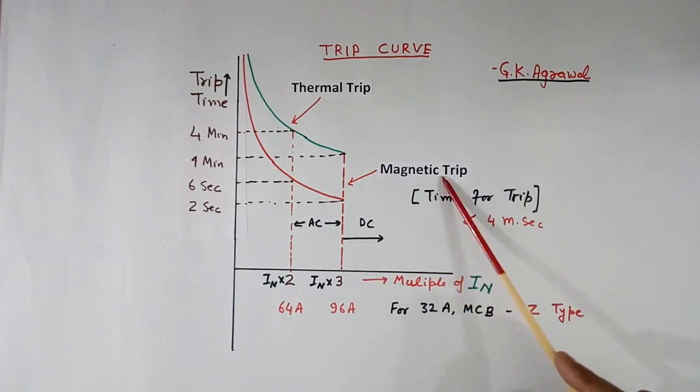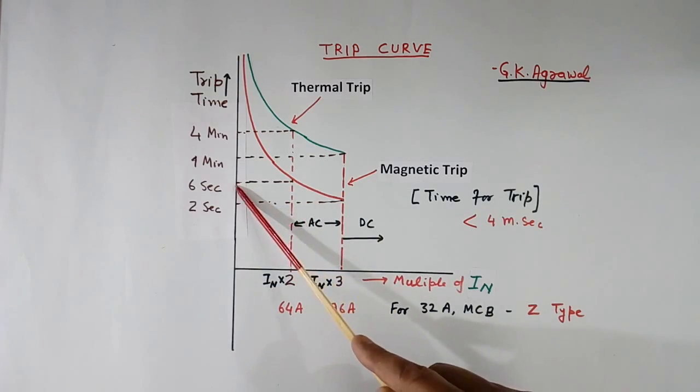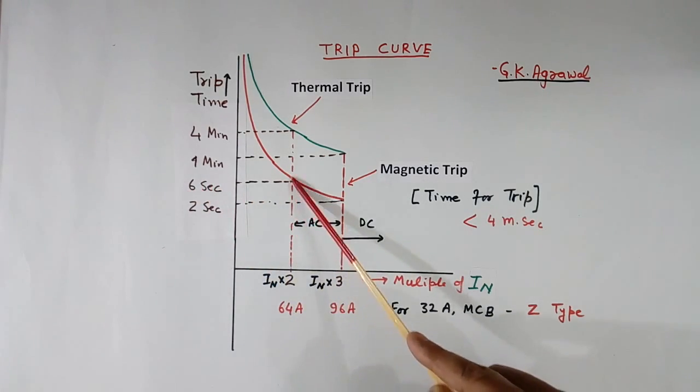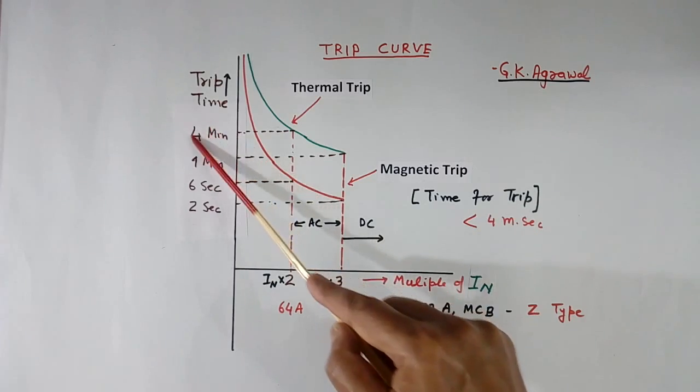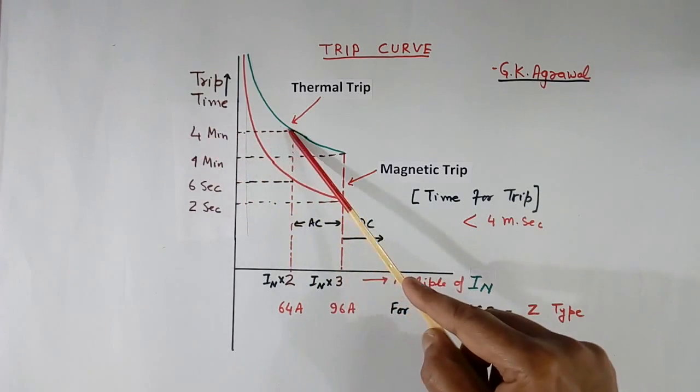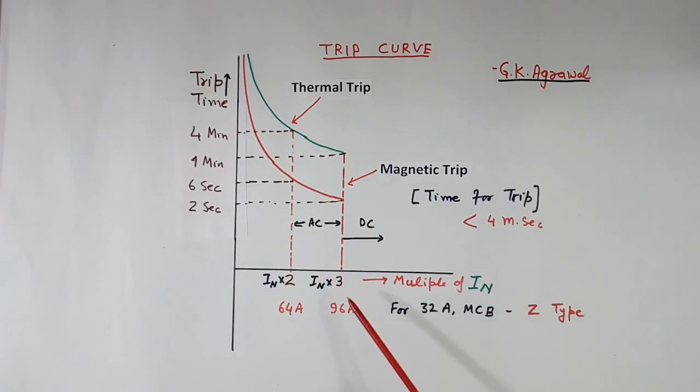And this is magnetic trip line. Now suppose double current flows, means for 32 ampere breaker, 64 ampere current flows. Then trip time can be 6 seconds to 4 minutes, anything. 4 minutes is maximum, worst case.